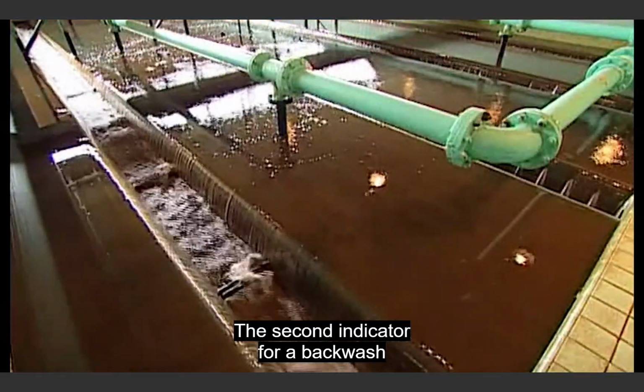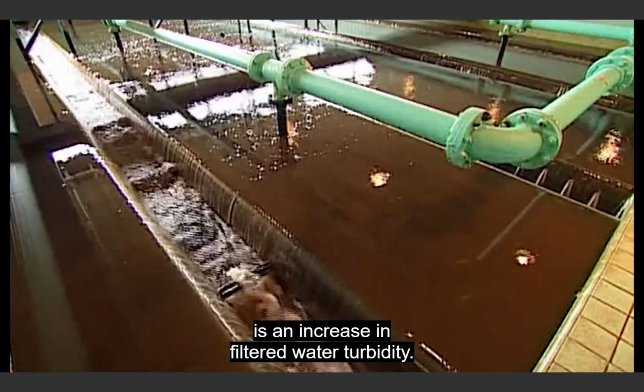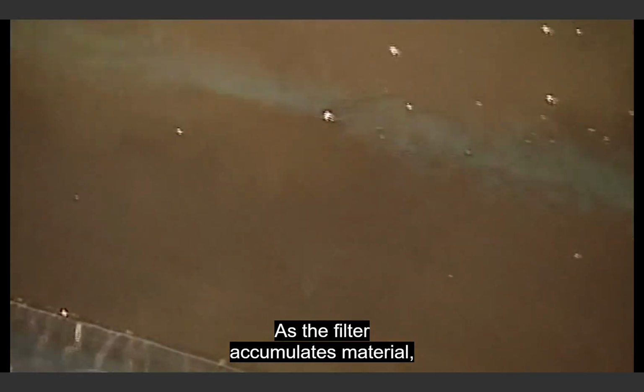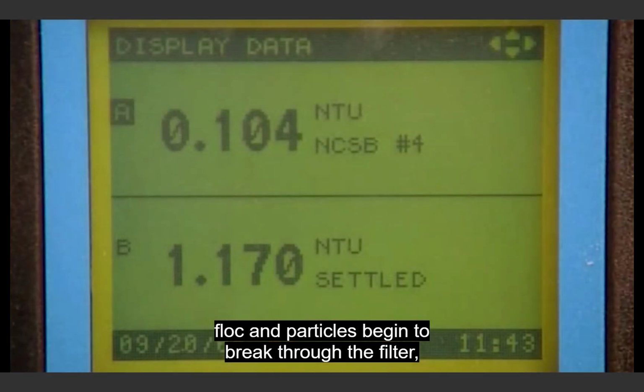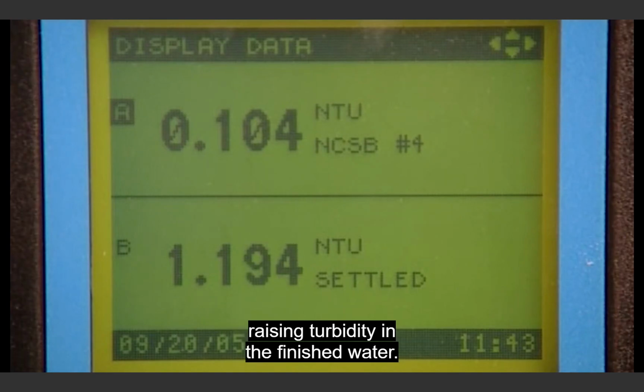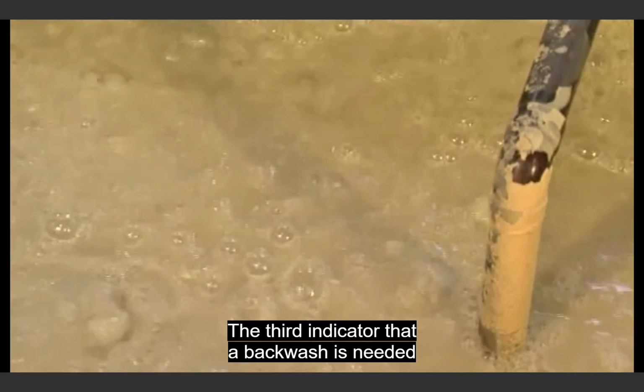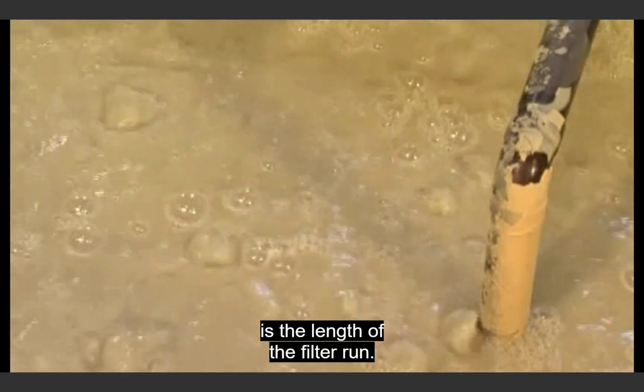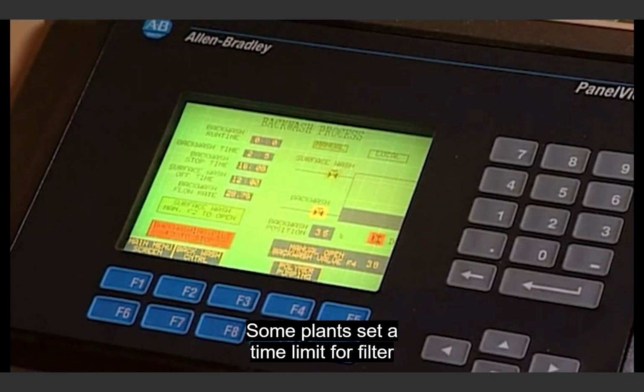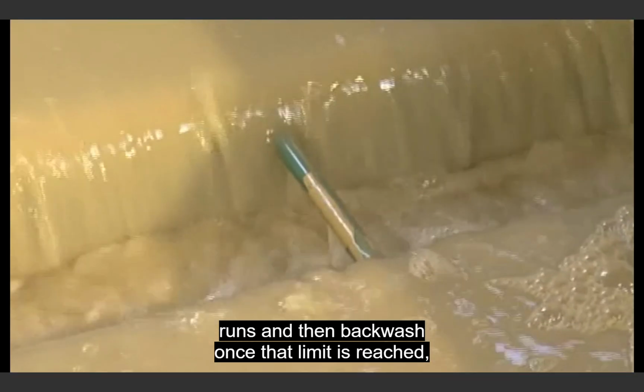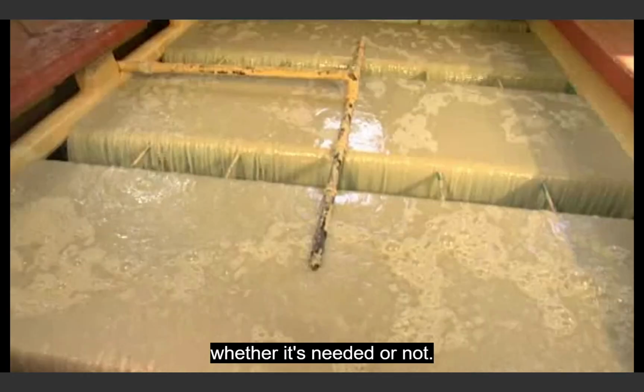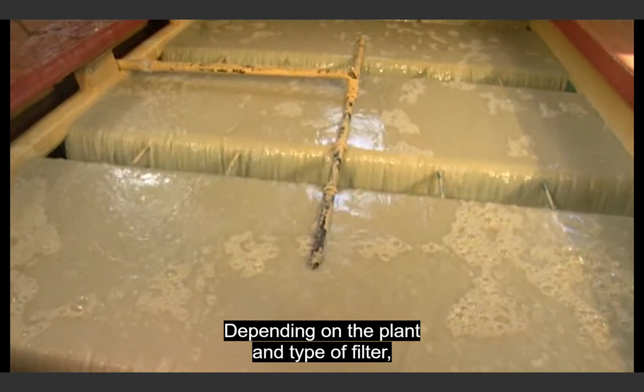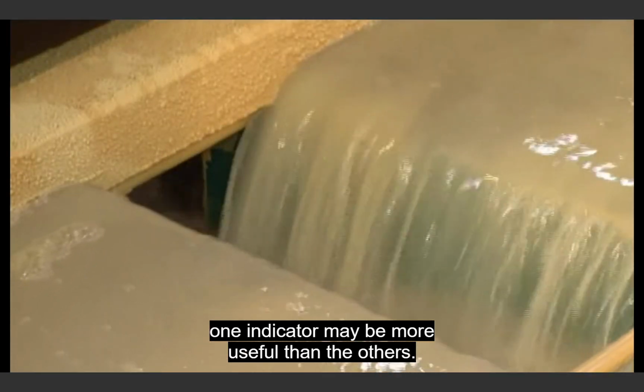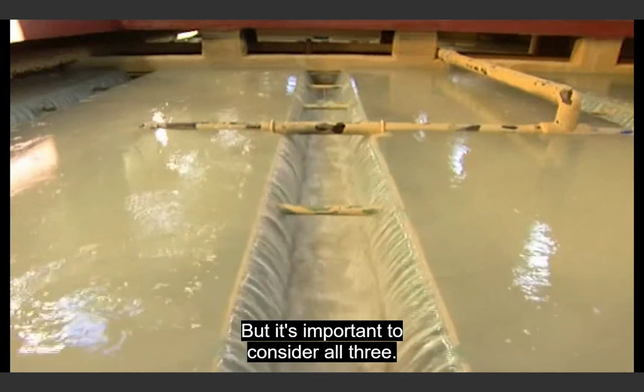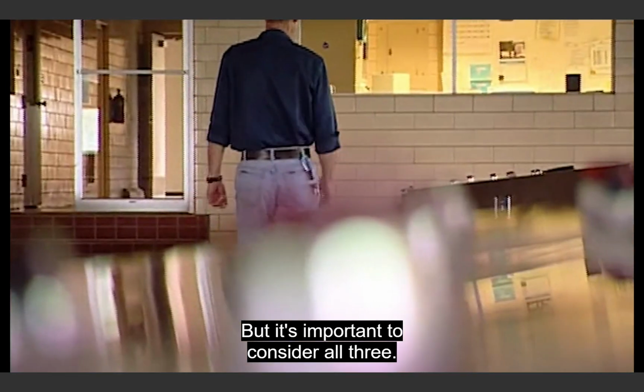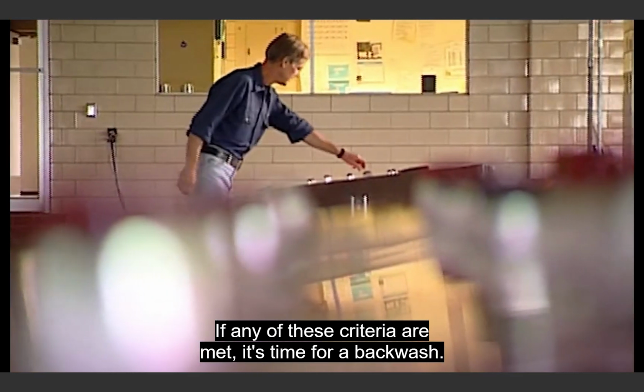The second indicator for a backwash is an increase in filtered water turbidity. As the filter accumulates material, floc and particles begin to break through the filter, raising turbidity in the finished water. The third indicator that a backwash is needed is the length of the filter run. Some plants set a time limit for filter runs and then backwash once that limit is reached, whether it's needed or not. Depending on the plant and type of filter, one indicator may be more useful than the others. But it's important to consider all three. If any of these criteria are met, it's time for a backwash.